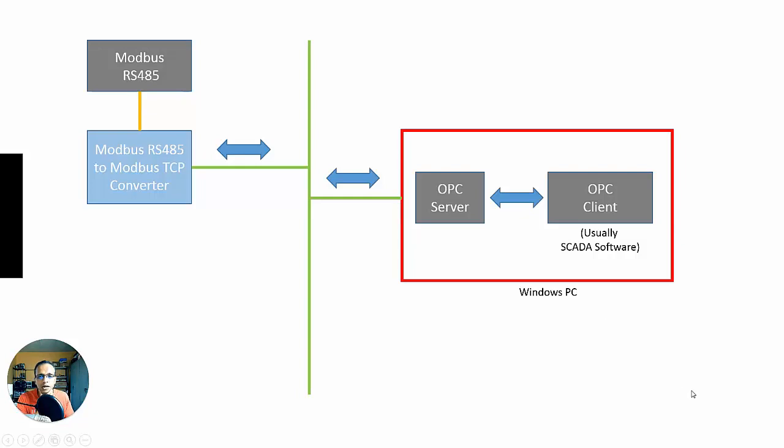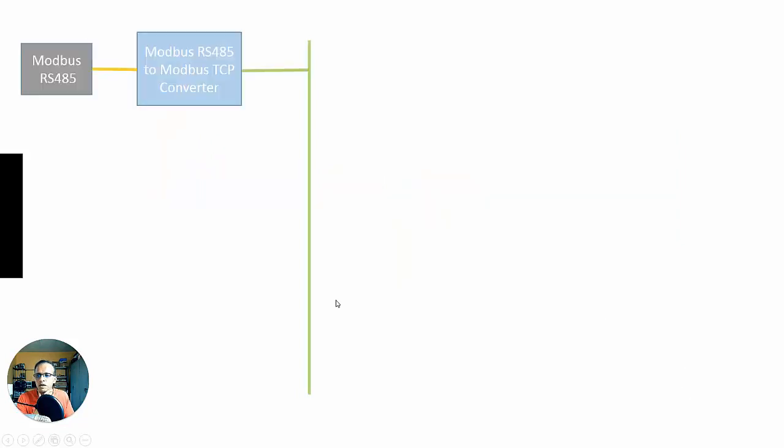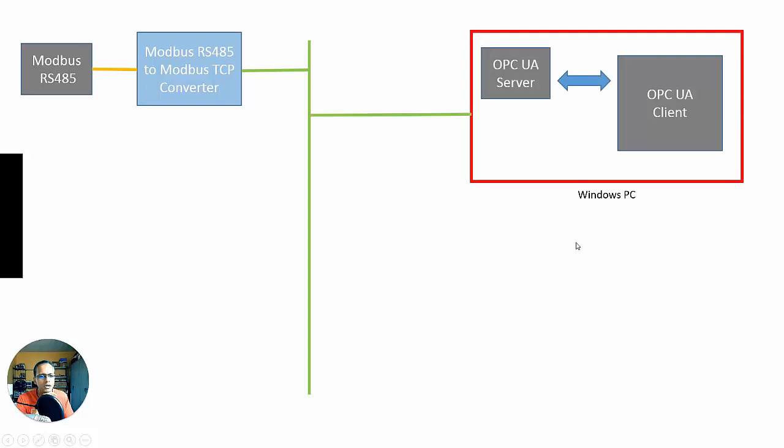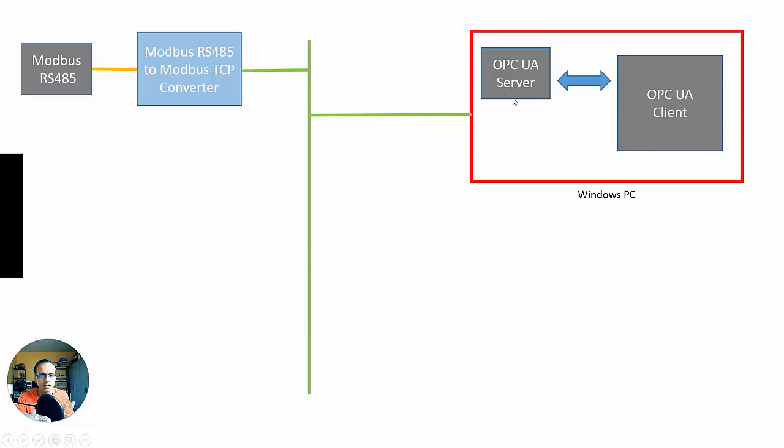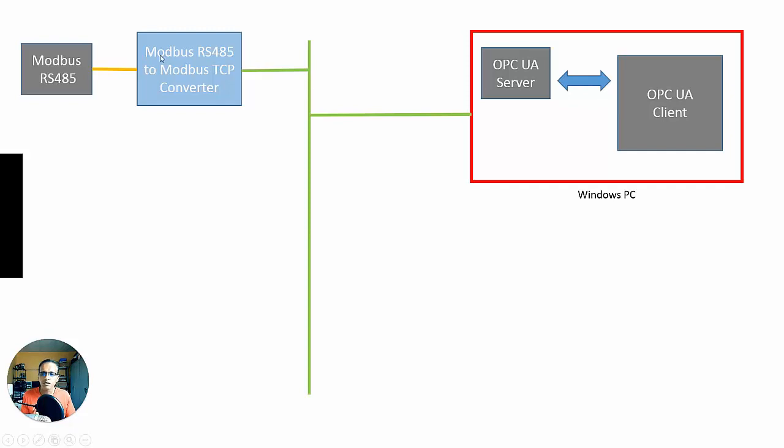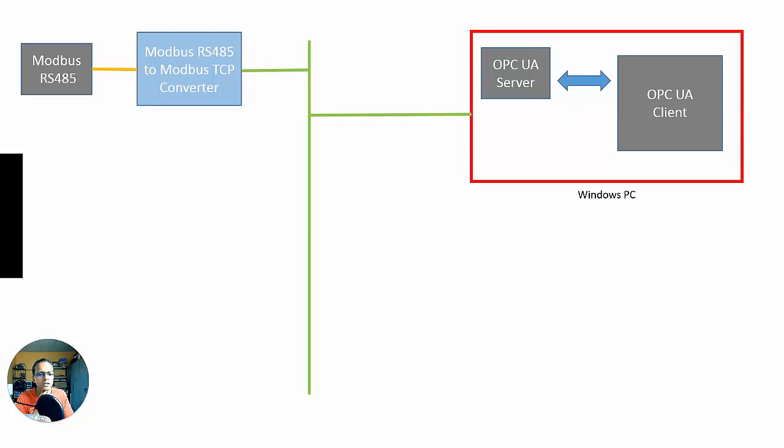All right, let's look at OPC UA. Similar scenario. I have my Modbus 485 device, my Modbus 485 to TCP converter, connected to my TCP network here. I have my same Windows PC, but now I have an OPC UA server and an OPC UA client. Now, this is doing the exact same thing. The OPC UA server is still acting like a protocol converter. It's communicating via Modbus TCP and getting all this data and converting it to the OPC UA standard, and the client is consuming that data.